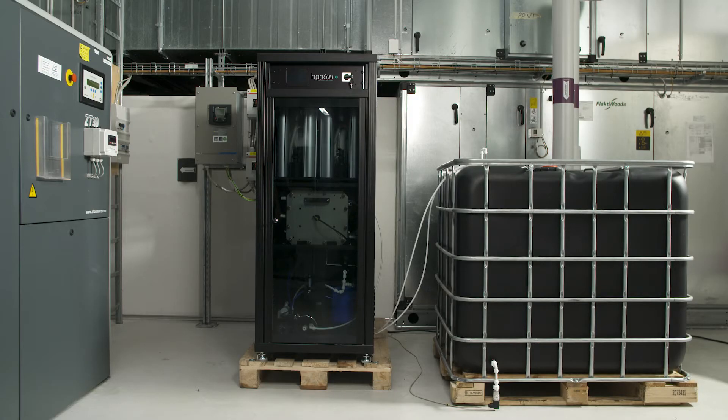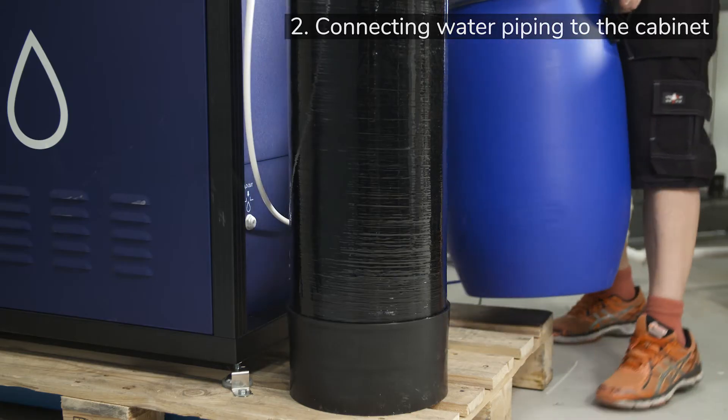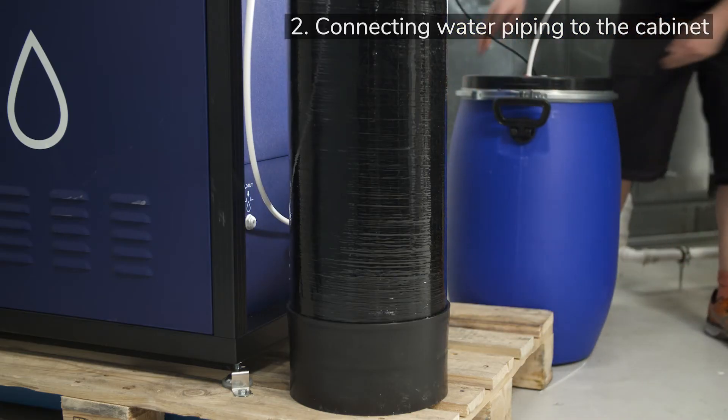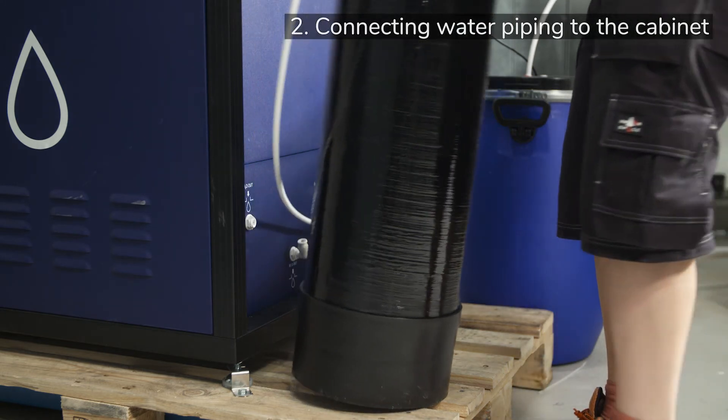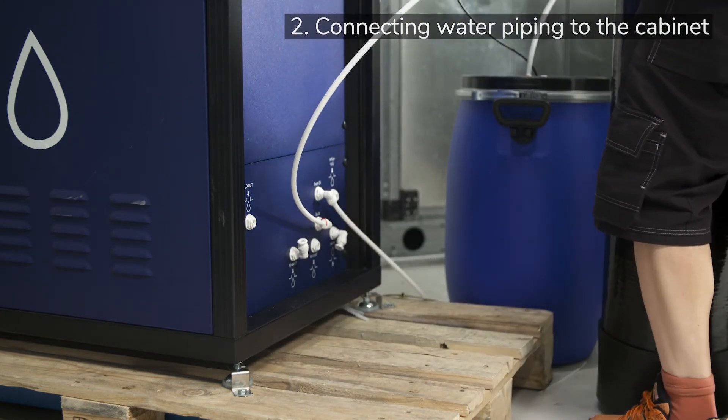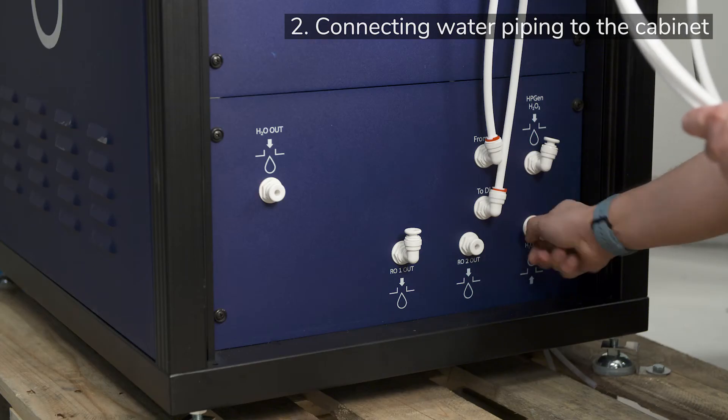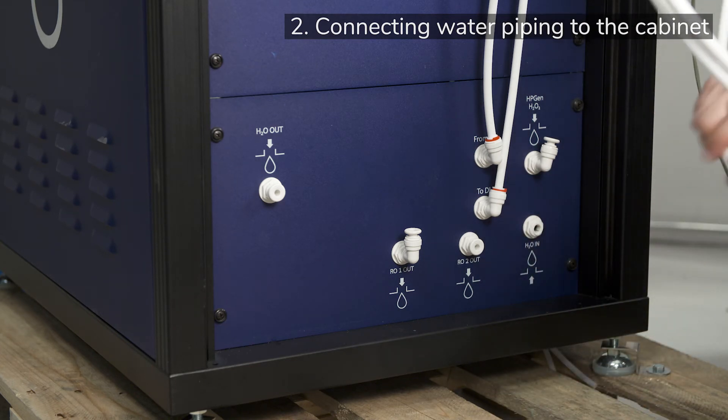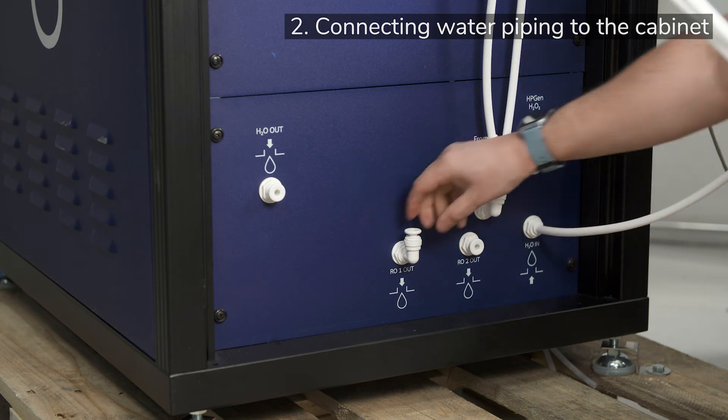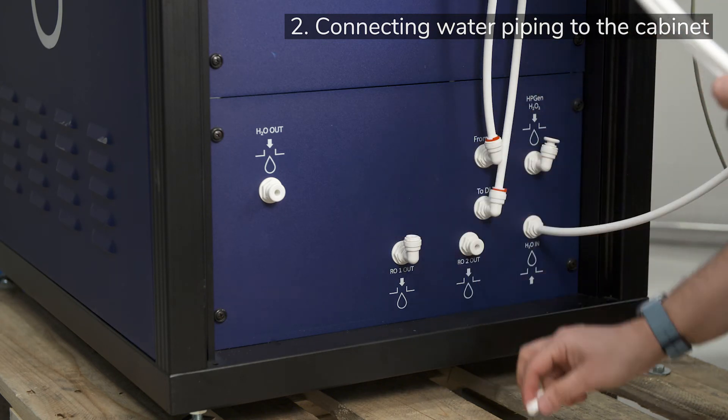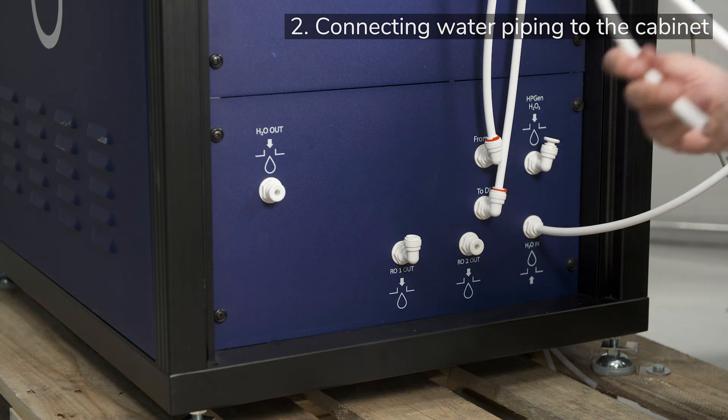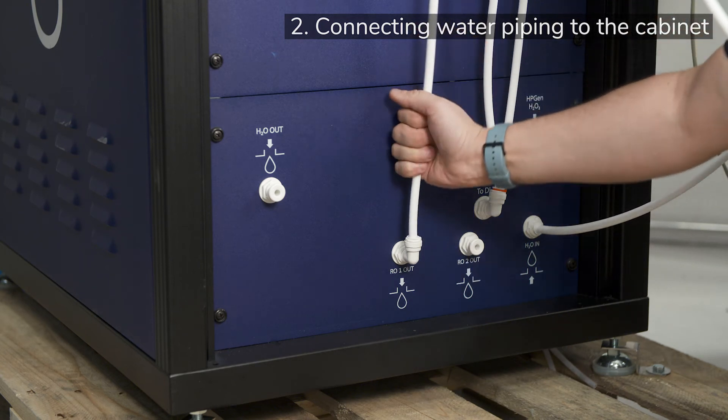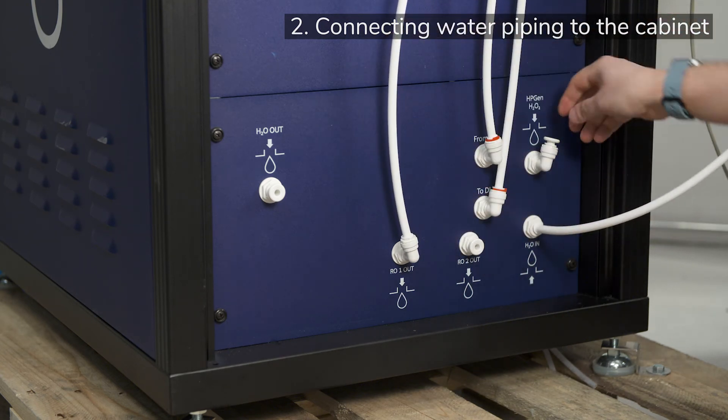Having prepared the reservoir, we now turn to connecting the tubing to the back of the HP Gen. First, move the pure water tank and DI resin column a little to the side for better access. With the back plate accessible, tubing can be connected. For each connection, start by removing the fitting stoppers by pushing in the ring underneath before pulling out the plug. These plugs are just there for transportation and must be removed before other tubing connections can be made.